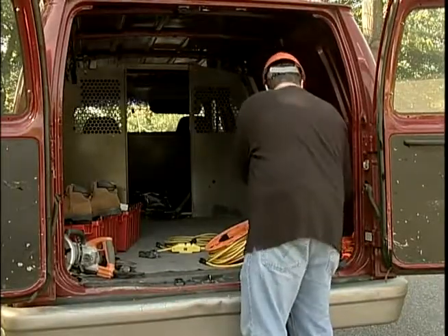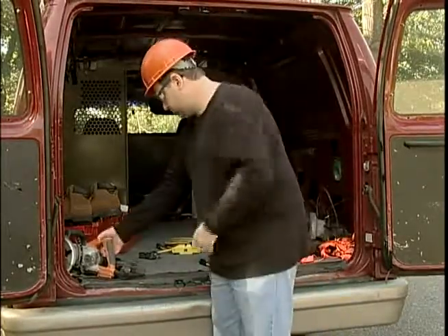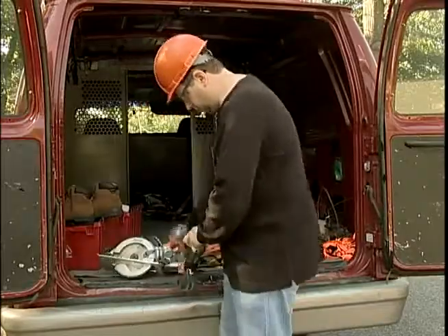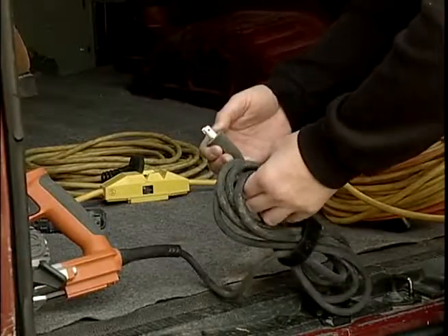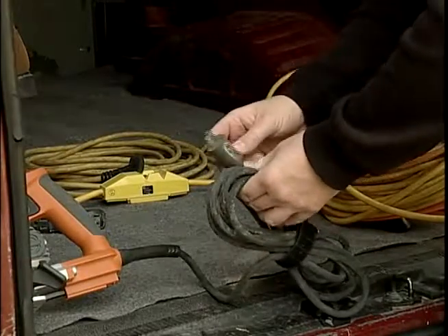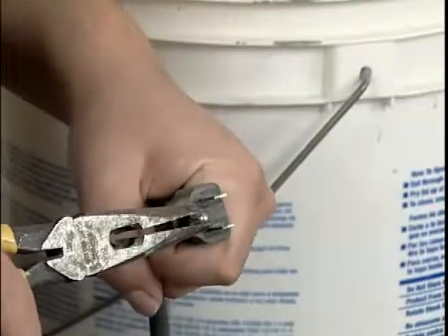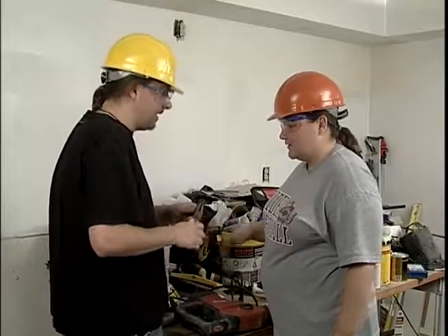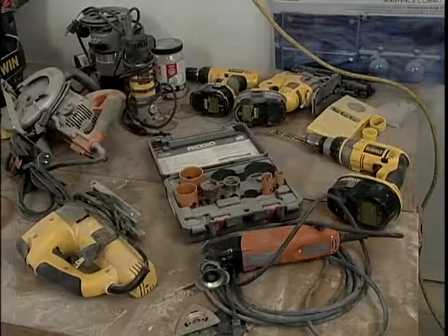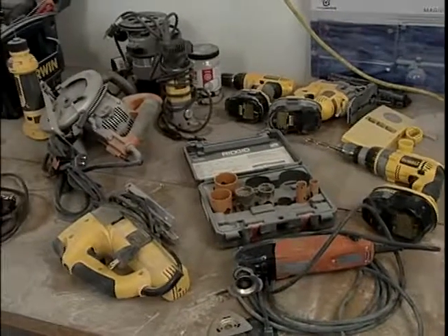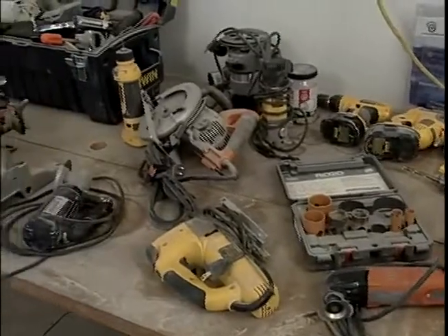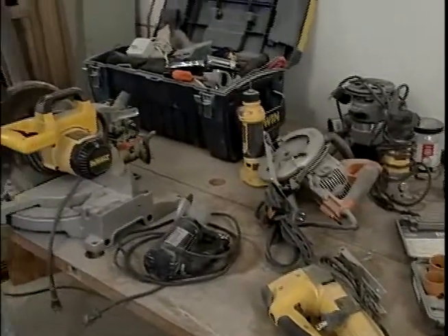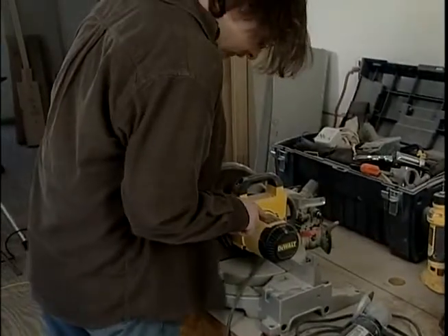Employers must ensure that any workers on the job site understand that it is their responsibility to inspect the electrical equipment they're working with before they use it. Workers must understand that ground prongs cannot be removed from tools or extension cords as well. Employers must also make sure that all electrical equipment that operates at 50 volts or more is effectively guarded so that workers do not accidentally come into contact with live parts.